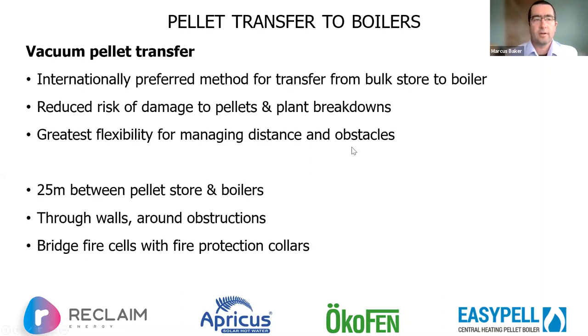And just in terms of how they're transferred, I'm a big fan of vacuum. I mean, vacuum is maybe a misnomer. Blower truck is maybe a better description. It's the international preferred method. It reduces risk of damage to the pellets, and also vacuum pellet transfer between the store and the boiler as well. So we're going to blow it into the store, and we're going to suck it from the store to the boiler. And that's where you really don't want to break down pellets and break down in the plant. It also gives us a lot of flexibility over distance and obstacles.